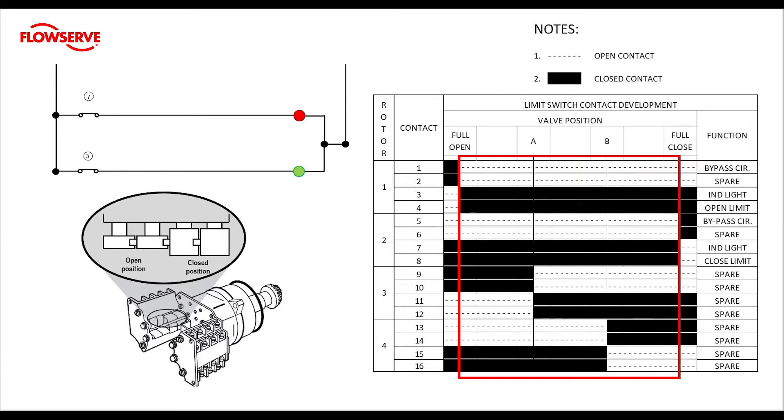This is due to the construction of the limit switch cams. Looking further down, we see that contacts five and six are also open in mid travel, while seven and eight are closed contacts. So now we know that in mid travel the limit contacts four and eight must be open. We also know that contacts three and four have the same action, so while in mid travel the green light fed by contact three is on. Contacts seven and eight have the same function, so while in mid travel the red light fed by contact seven is also on.